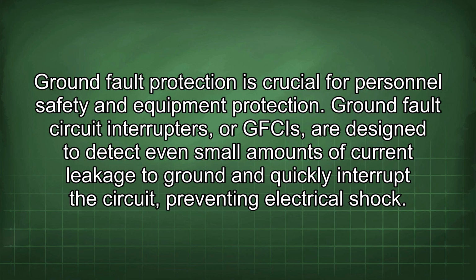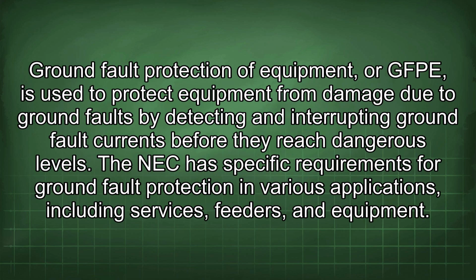Ground fault circuit interrupters, or GFCIs, are designed to detect even small amounts of current leakage to ground and quickly interrupt the circuit, preventing electrical shock. Ground fault protection of equipment, or GFPE, is used to protect equipment from damage due to ground faults by detecting and interrupting ground fault currents before they reach dangerous levels. The NEC has specific requirements for ground fault protection in various applications, including services, feeders, and equipment.